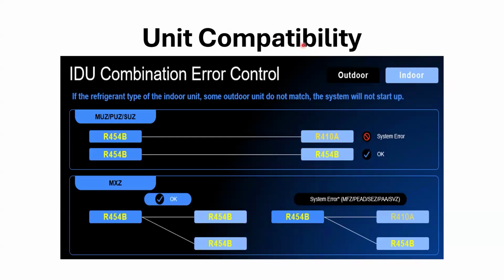Again, going back to compatibility. Indoor unit combination error control. If the refrigerant type of the indoor unit and some outdoor units do not match, the system will not start up. So basically, like I was saying, it's a no-go. There's no way around it. You can't mix that equipment.